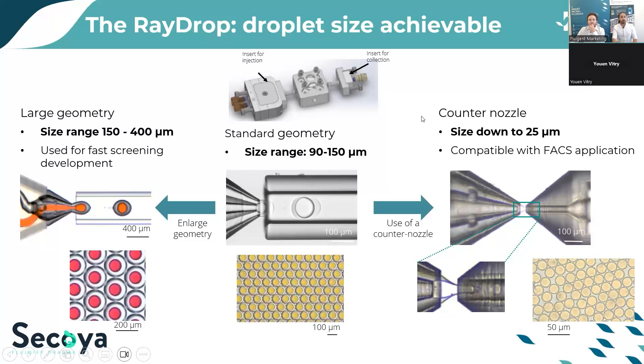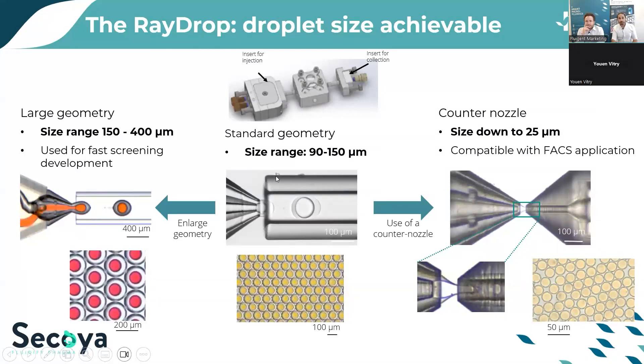For applications requiring smaller double emulsions — such as encapsulating cells or bacteria for FACS sorting — the double emulsion must be smaller than the FACS nozzle to avoid breakage. For this, we developed another design called the counter nozzle: the same double nozzle inlet is used, but at the outlet, instead of a collection capillary, a counter nozzle increases local shear stress, generating smaller double emulsions at a higher generation frequency. This allows targeting double emulsions from 25 micrometers in diameter.